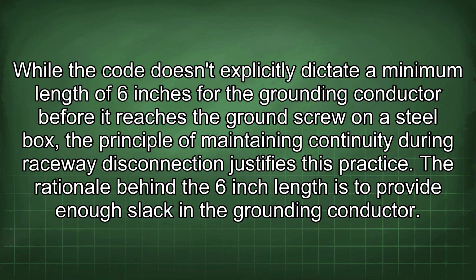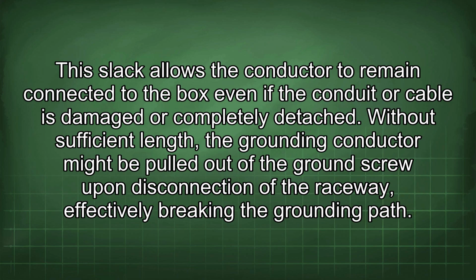The rationale behind the 6-inch length is to provide enough slack in the grounding conductor. This slack allows the conductor to remain connected to the box even if the conduit or cable is damaged or completely detached. Without sufficient length, the grounding conductor might be pulled out of the ground screw upon disconnection of the raceway, effectively breaking the grounding path.